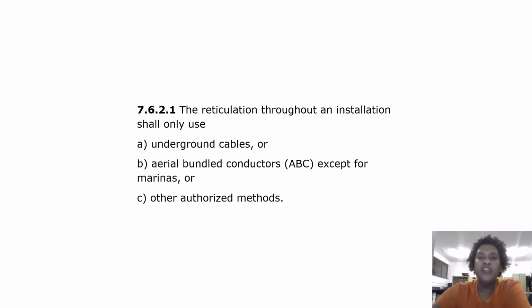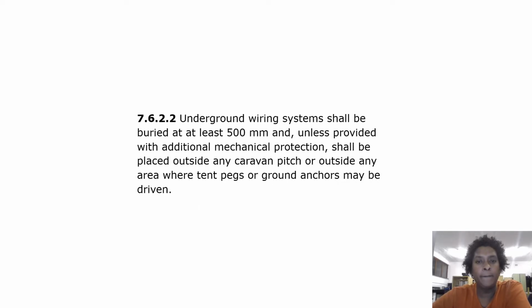Reticulation. The reticulation throughout an installation shall only use underground cables or aerial bundled conductors, except for marinas or other authorized methods. Underground wiring systems shall be buried at least 500 millimeters and, unless provided with additional mechanical protection, shall be placed outside any caravan pitch or outside any area where tent pegs or ground anchors may be driven.